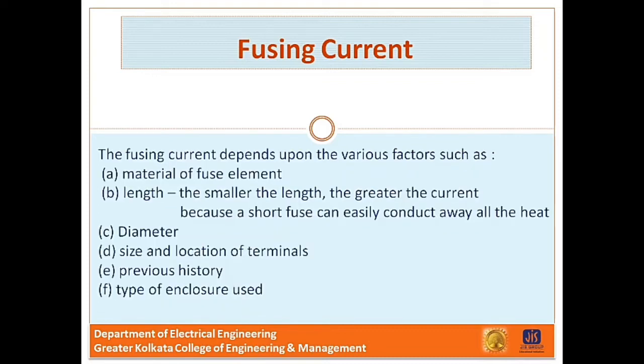The fusing current depends upon various factors. First, the material of the fuse element. Next, length — the smaller the length, the greater the current, because a short fuse can easily conduct away all the heat. Fusing current also depends on diameter, size, location of the terminals, its previous history, and the type of enclosure used.